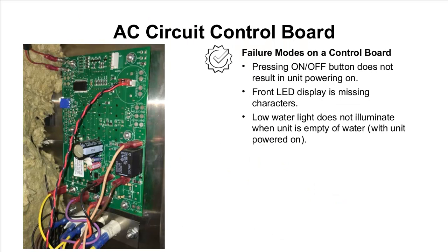A few quick things to recognize a problem with the control board without actually testing anything. Obviously, if you push the on-off button, the unit does not power on, and you have no alarms going off whatsoever, that could be an issue with the board. We're going to want to test the power coming in. If the LED display on the front of the board that the customer can see is missing characters, again, it is a sign that the board should be replaced.